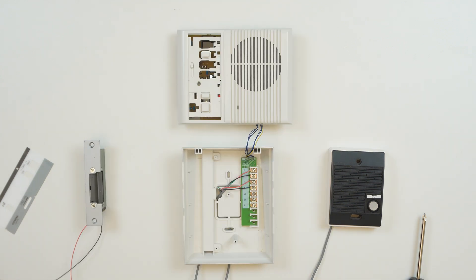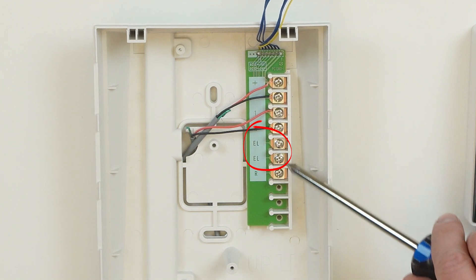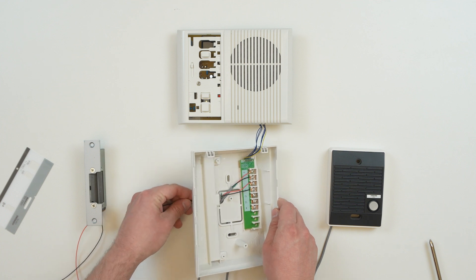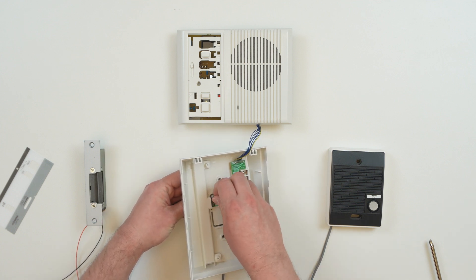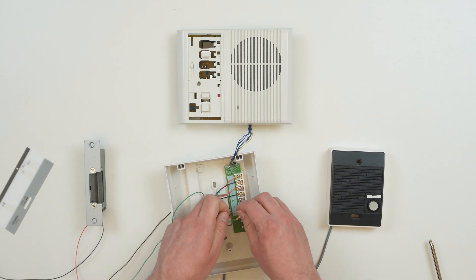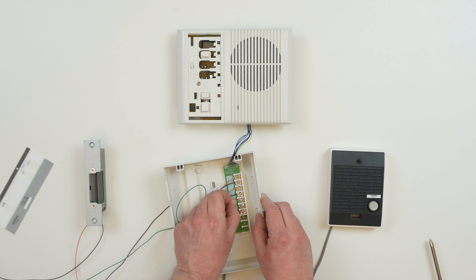The door release terminals are labeled EL and EL. This is a normally open, dry contact, and the two terminals are non-polar. This means that it does not matter whether positive or negative wires are run through them. These can either be wired in series with the door strike and its power supply, or connected directly to an input on an access control system.